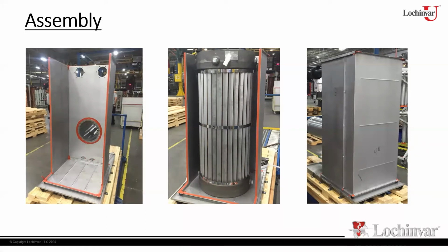So we start with our base. They put our frame, if you will, the sheet metal, or in this case stainless steel box that forms our combustion chamber. The heat exchanger goes into that, and then we seal up the front door. So you see the completed box over here on the right side. Now, once we put the front door on, we're going to pressurize that cabinet to ensure that there are no leaks. So they're going to basically plug off the vent side. They'll put a big plug, if you will, in the back end here. They'll put a plate on the top of it, covering up the combustion chamber with an air spigot, and basically slightly pressurize that cabinet, and then check for leaks along the seams. This needs to be sealed airtight.